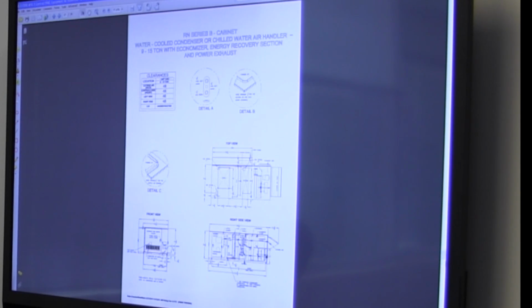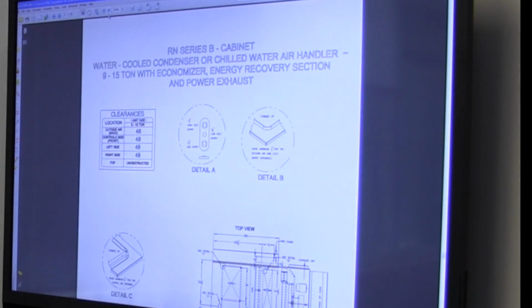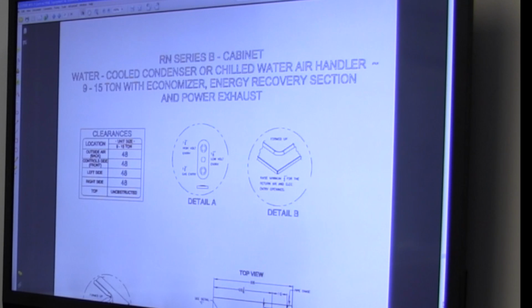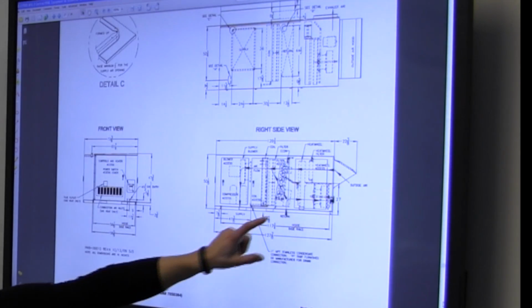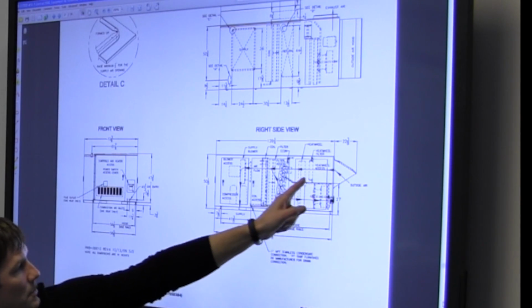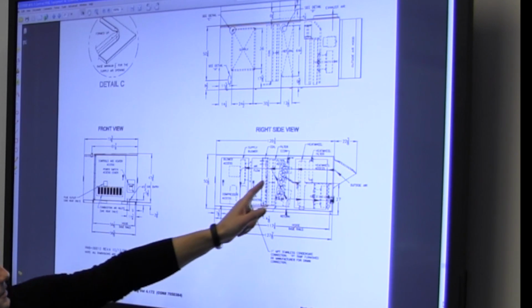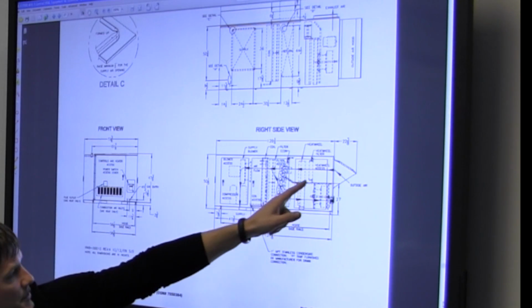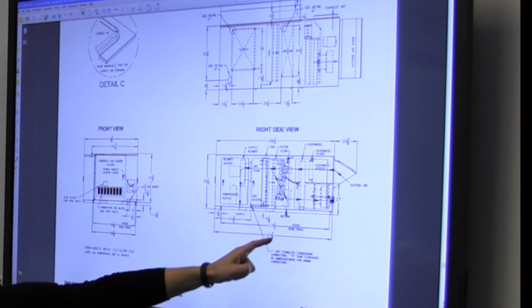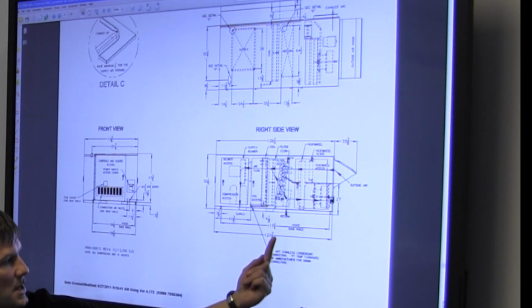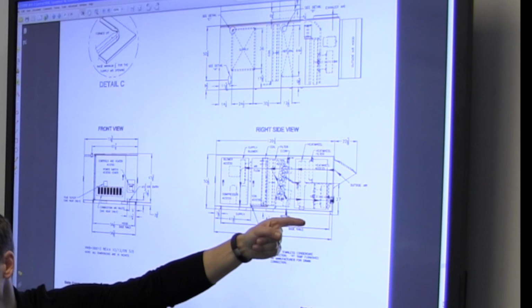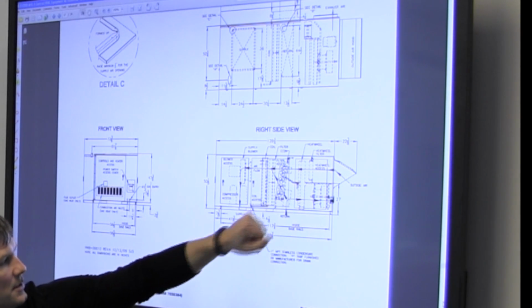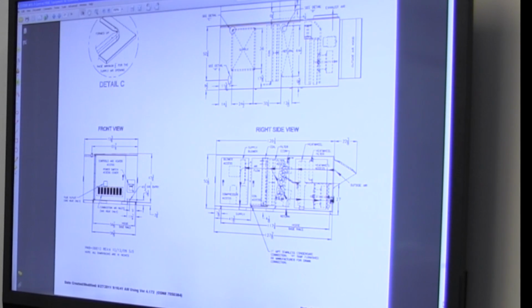And the smaller unit looks about the same. It doesn't have the large heat wheel in the back. It does have a heat wheel, it's just not as big. So it's a constant size. It goes through the heat wheel. Here it shows the heat wheel filter. On the other one, it just didn't show it. There's also a filter rack here to filter the exhaust air that's coming up before it goes through the wheel, so the wheel doesn't get plugged up. So there's a filter rack down here as well. Pretty much the same unit.